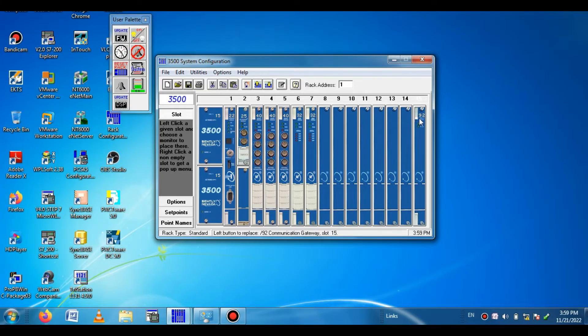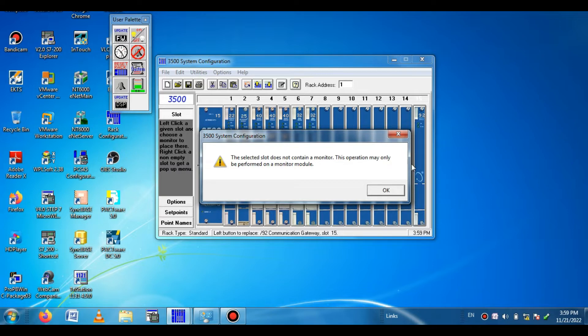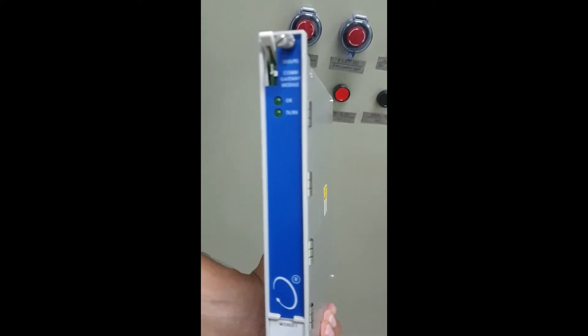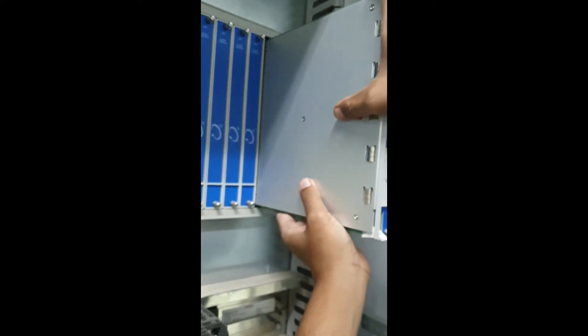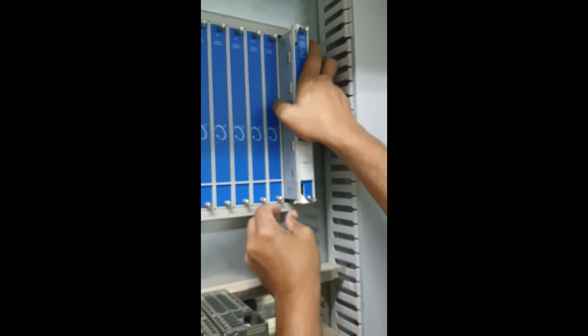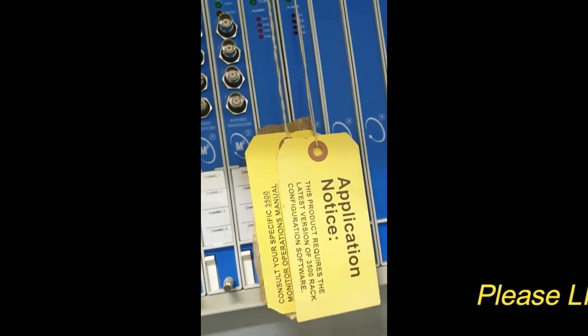I have to tell you that if you want to change any module card, after opening the old module card I show what is displayed in the configuration software. Here you can see that the selected slot does not contain any card, so we cannot go to verification — meaning the card is removed. Now I insert the new card in the selected slot. You must remember to use the same part number or same card as a replacement for the damaged or faulty one. Now I am replacing with the new card and inserting it — you have to press this card in firmly.